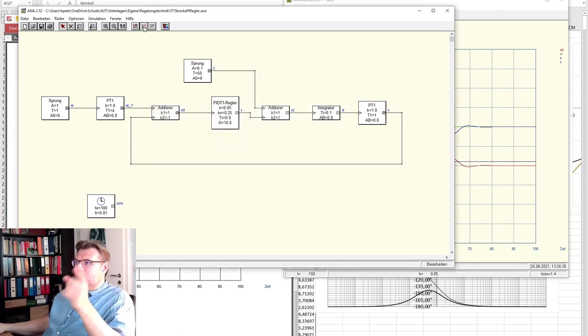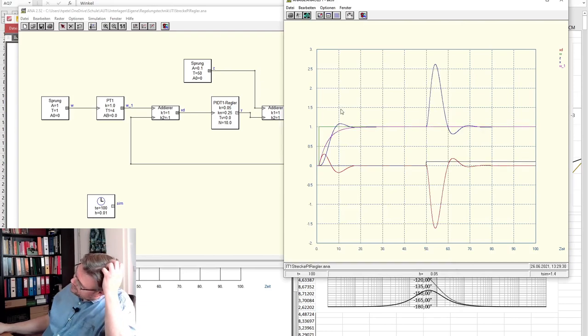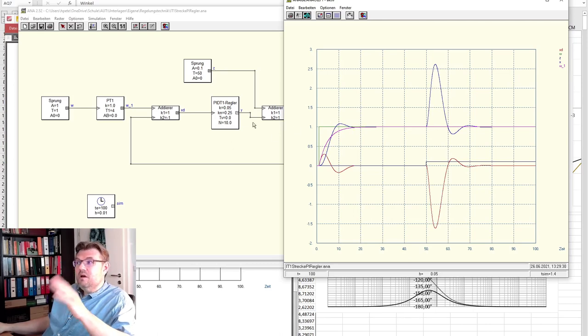and I'm looking now at what is happening, you see what happened. What do we see here? This green line is still the reference value. After the filter, it's the purple line. So the purple line is the desired value which the controller is working with. And this helps the overswing tremendously, because it is not already there. It will appear slowly. This overswing is still done by the controller. However, the set point is compensating this.